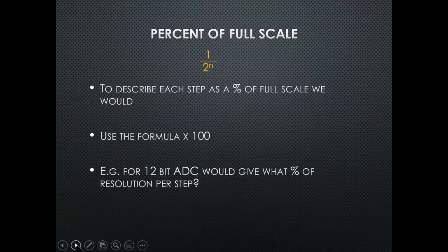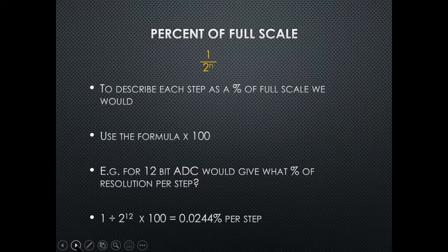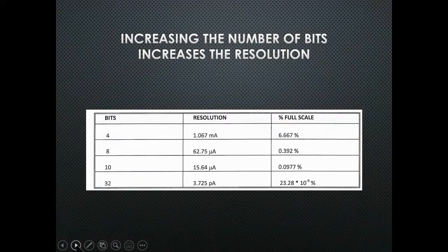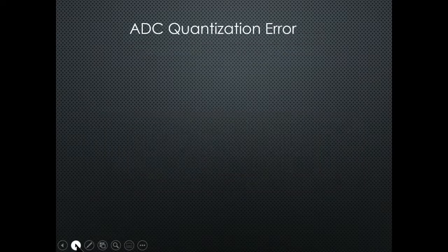For a 12-bit ADC: 1 ÷ 2¹² × 100 = 0.0244% per step — that's high resolution. Increasing the number of bits increases the resolution. A 4-bit system gives resolution of 1.067 milliamps per step; 8-bit gives 62.75 microamps; 10-bit gives 15.64 microamps. As the number of bits increases, the resolution increases.